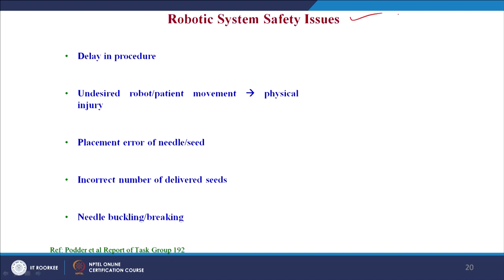Now coming to the safety issues associated with robotic systems: delay in procedure, undesired movement of the robotic system disturbing or harming patients or clinical staff, anatomical movement of the patient damaging instrumentation, placement error of the needle or seed, incorrect number of delivered seeds, and finally needle buckling or breaking — needle buckling being the strong bending of the needle with sharp edge or breakage. These are the safety issues encountered in robot-assisted percutaneous needling interventions.